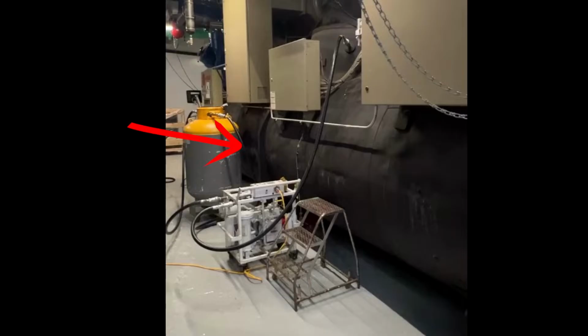So it'll kind of flutter around, and you'll see the hose physically moving. What you're seeing is the liquid refrigerant traveling through that loose hose, and it's heavy enough to cause the hose to have some movement. You can actually hold your hand on it and feel that liquid going through there once you understand what you're feeling for. So if that hose is still dancing around a little bit, and it's not always much, then you know that liquid is still processing through there.